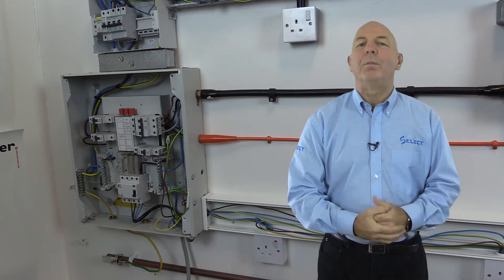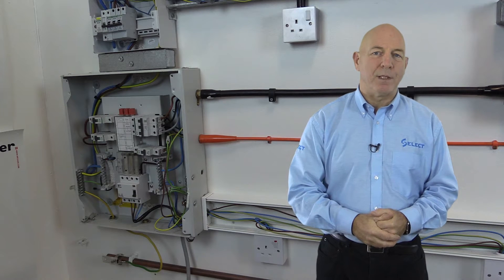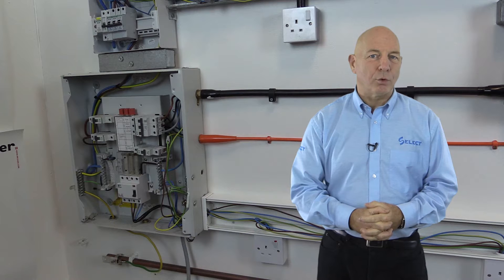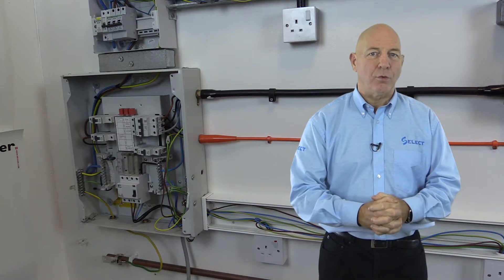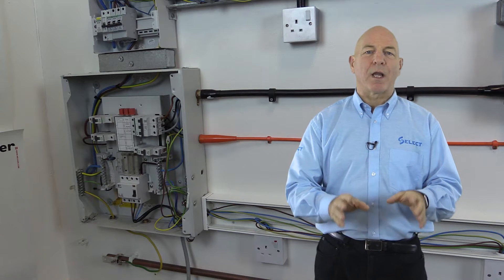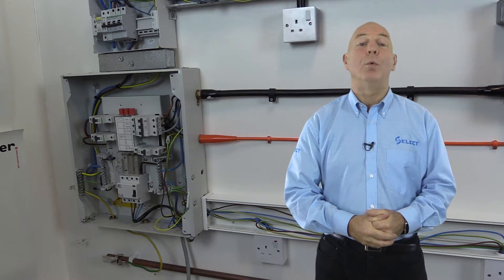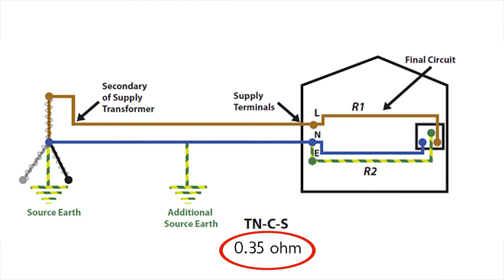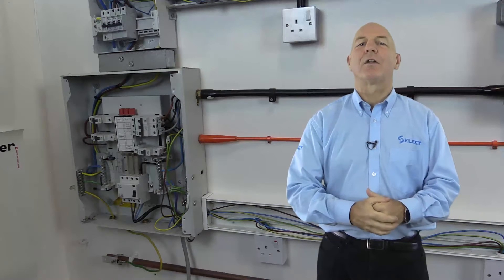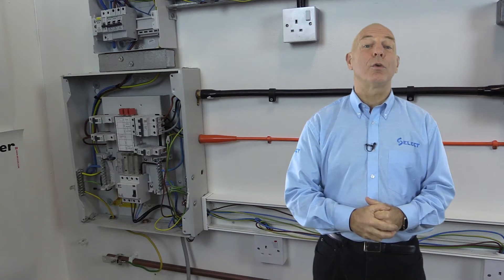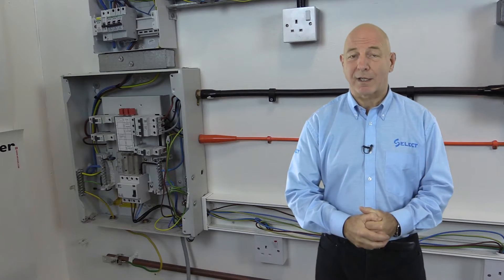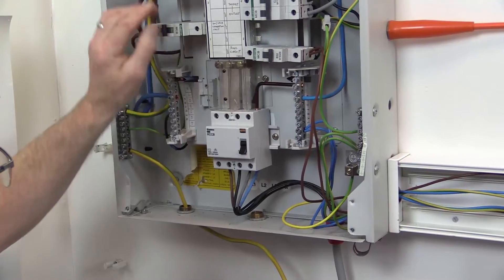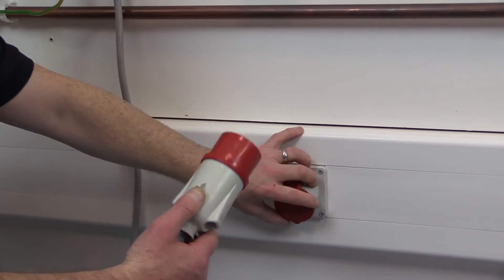The first part of the test will be to verify the external earth fault loop impedance, known as ZE, which is that part of the earth fault loop impedance path external to the installation. This can be determined by inquiry by contacting the distribution network operator, who will provide industry values. For a TN-S system this can be up to 0.8 ohms, and for a TN-C-S system it can be up to 0.35 ohms. It's recommended that a test of earth fault loop impedance is made to ensure that the distributor's earth terminal is actually connected to earth. This is a power-on test, so great care is necessary to ensure safety during the test.